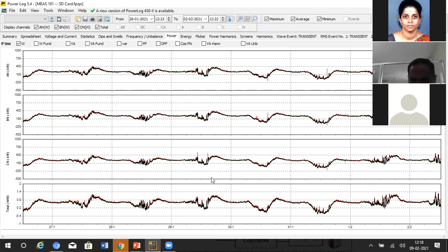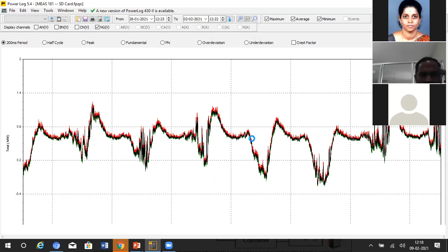Just see this, some of the time we are injecting the power back. See, this is the zero level. I hope you can see my cursor. I think this is a holiday, the 30th and 31st, Saturday, Sunday maybe. So during peak hours, that is 11 to 2 p.m., I'm injecting the power back to the grid. That's what you are seeing here. The quantity is somewhere around minus 300 kilowatt, I'm supplying to the grid. And if you see the current pattern, you can understand the character of solar PV and its impacts.